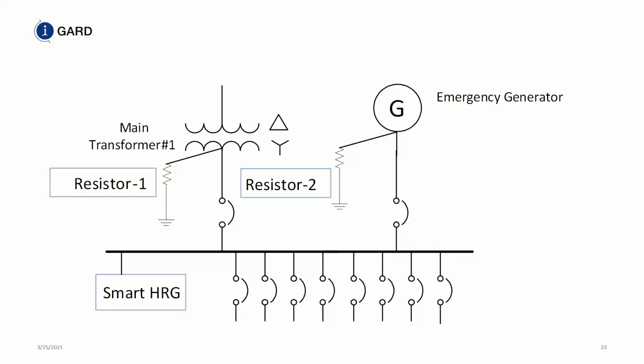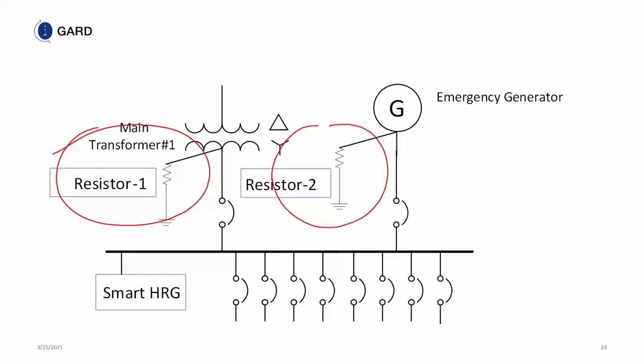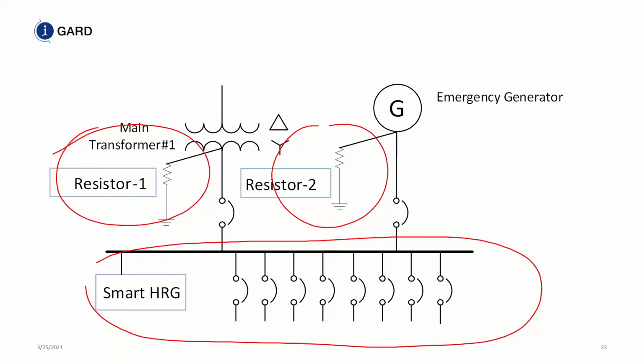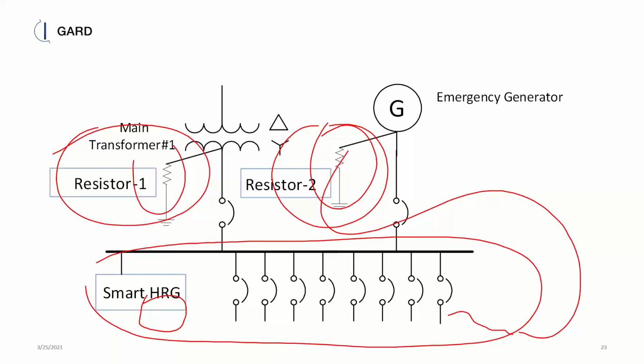So now our topology changes. We can have a resistor on the transformer, a resistor on the generator, a smart HRG system on the bus. So this is where our HRG system is. To me, this resistor is just a return path. The only thing I'm going to use that for is if the generator is on, the return path current is through the generator. If the utility is on, then the return path is through the utility. As far as the HRG system is concerned, it's irrelevant what the source is that's on. I'm looking for the ground fault current in the load because most of the ground faults are going to be in the loads and not the sources. The sources get the added benefit of being monitored and protected, but I'm more concerned with the loads.